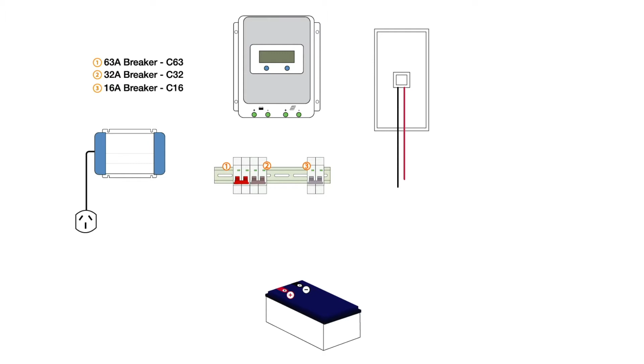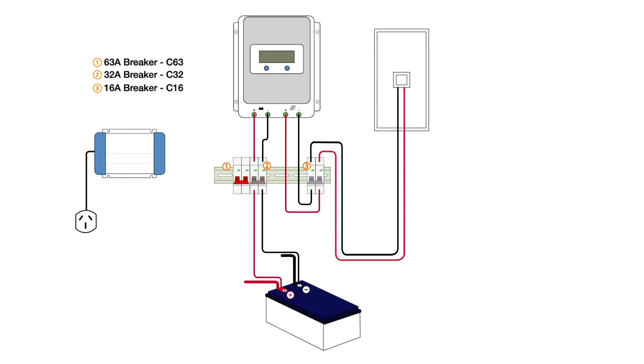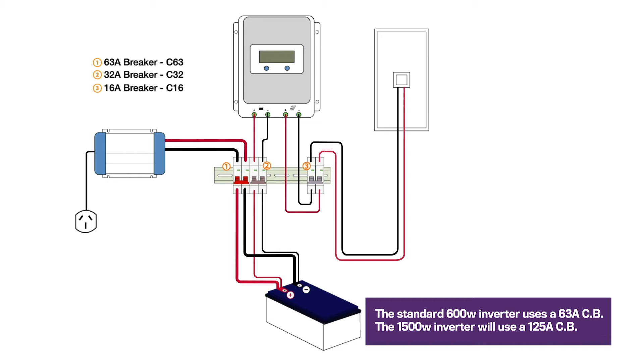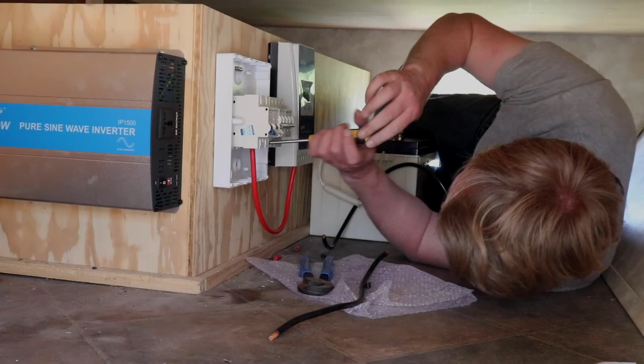We're going to finish running our solar cables down into this little cubby, into the circuit breaker, through that circuit breaker into this charge controller. Then we'll run the battery circuit from this charge controller through our circuit breaker to the battery. The last circuit goes from this battery through the last 125 amp circuit breaker and into the inverter—that'll be the final wiring for the DC side of this install.